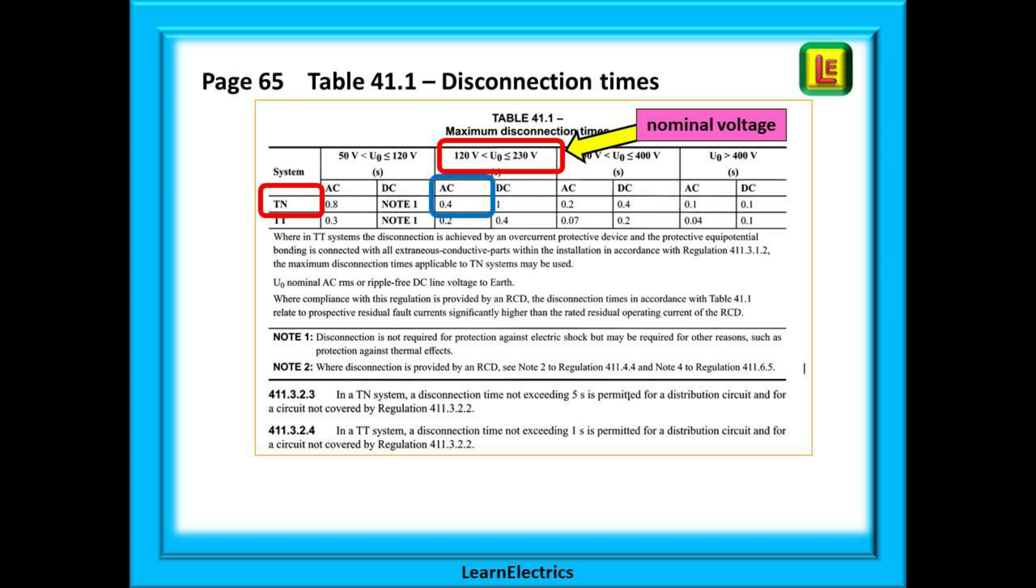For the kitchen, a 230 volts nominal, we will use the second block of data. The symbols at the top say the nominal voltage is over 120 volts and up to and including 230 volts. On the left, we can choose the earthing system. Let us use TN which is shorthand for TNCS or TNS. Where the column and row cross, we have 0.4 seconds. This is our maximum disconnection time for that particular installation, 0.4 seconds.